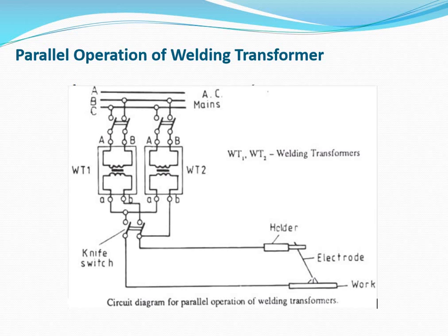Now here one thing should be noted: welding transformers have a rather low power factor due to the fact that they incorporate coils having high inductive reactances. Therefore, a welding transformer must not have a power rating higher than necessary for the performance of the assigned job, and it should not run at no load for a long time.